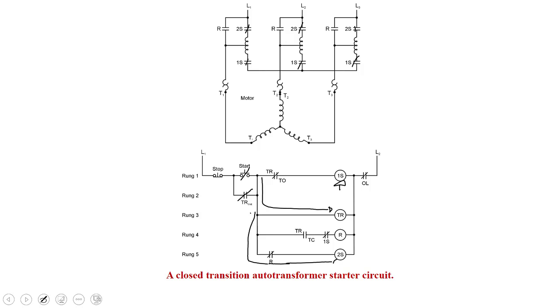Okay. So this contact is open, and this 1S contact is also open here because 1S is energized. That's a normally closed contact, so we call that an interlock. So 2 of them are open in series then. So what happens when the timer times out? Okay, the timer times out, so that means its contacts are going to change state. Starting at the top, TR, this first one, will open. All right, so that controls contact 1S. So 1S opens.